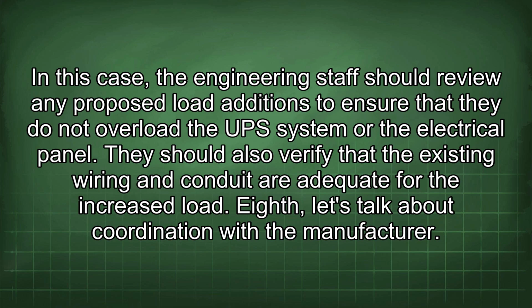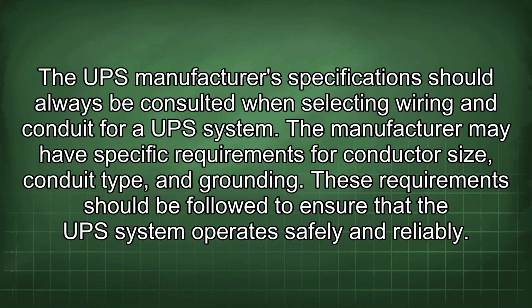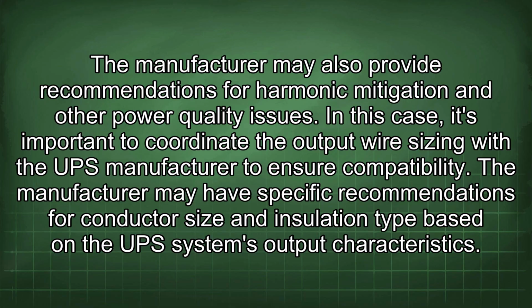Eighth, let's talk about coordination with the manufacturer. The UPS manufacturer's specifications should always be consulted when selecting wiring and conduit for a UPS system. The manufacturer may have specific requirements for conductor size, conduit type, and grounding. These requirements should be followed to ensure that the UPS system operates safely and reliably. The manufacturer may also provide recommendations for harmonic mitigation and other power quality issues. In this case, it's important to coordinate the output wire sizing with the UPS manufacturer to ensure compatibility. The manufacturer may have specific recommendations for conductor size and insulation type based on the UPS system's output characteristics.